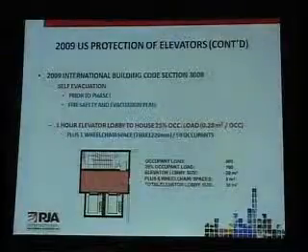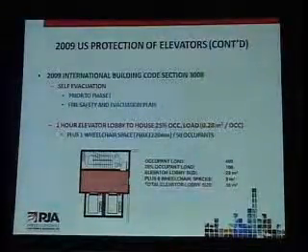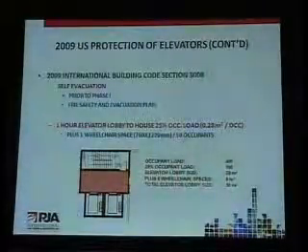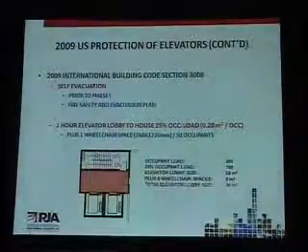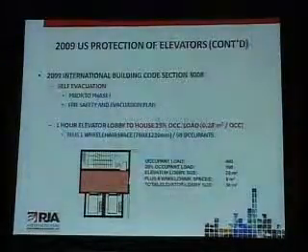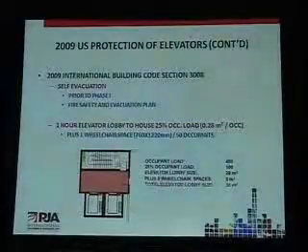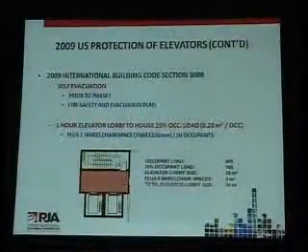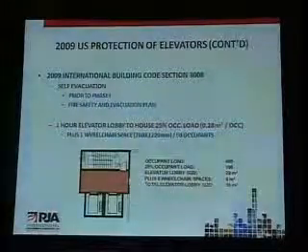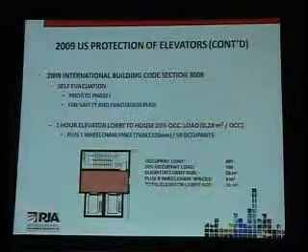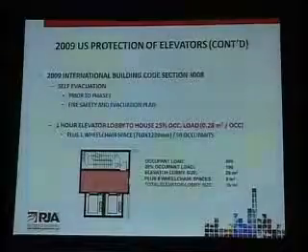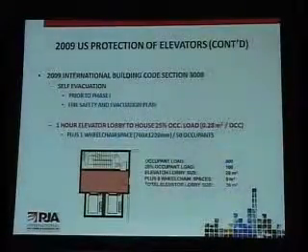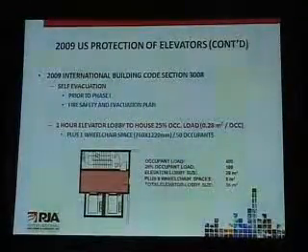So going into the actual protection of it and some of the planning issues that come along with it, this is something that any architects in the crowd are going to want to pay attention to: the size requirements for the vestibule. Vestibules can be fairly small. Typically, when you're looking at a firefighter shaft, you're looking at a service vestibule that's really only sized to accommodate services coming in and out. Well, now you have an actual requirement based on the occupant load of your floor.